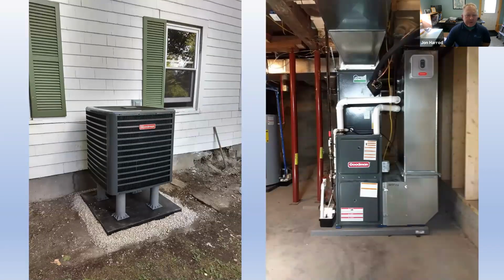Here is an example of one of these installed. We have the outdoor unit. It's up on heat pump legs to keep it out of the snow because it's going to be operating in colder weather. And here's the indoor unit. We have a high efficiency natural gas furnace. The indoor coil sits on top of that. And as you can see, we've enlarged the return ductwork because heat pumps need more airflow than fossil fuel equipment. So in almost all cases, we're doing some kind of ductwork modification to make sure that these are getting adequate airflow.